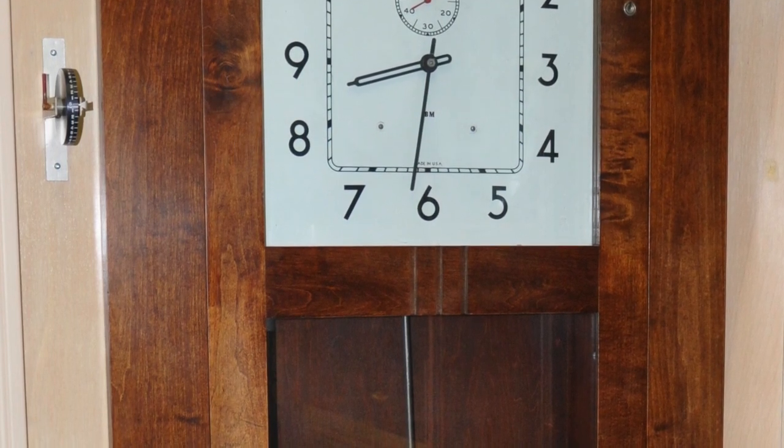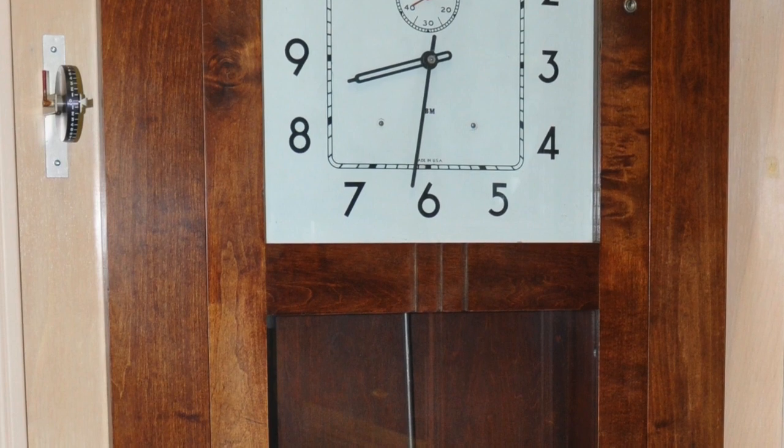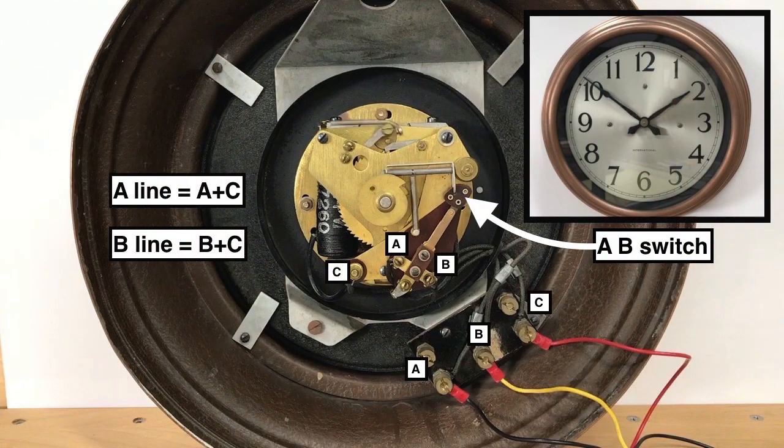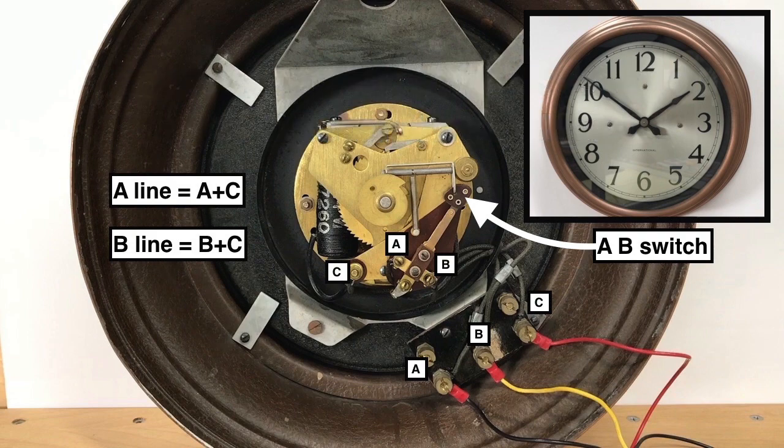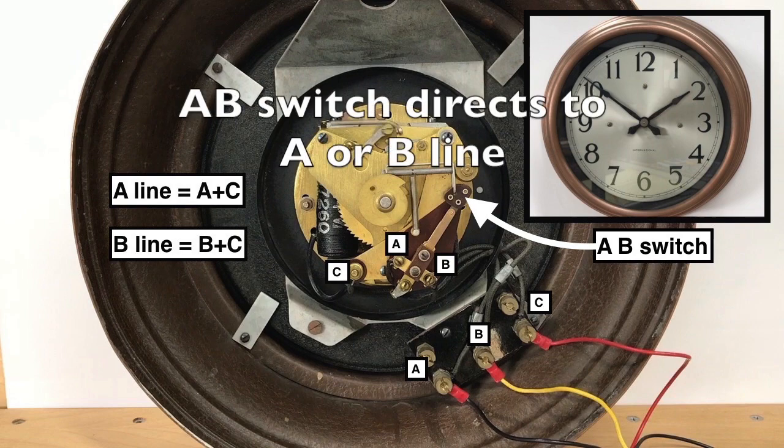The slave clock is not an independent timepiece. Slave hands are simply advanced one minute each time they receive an impulse from the master. This shows the slave wiring. The slave only accepts impulses on one line or the other. The A-B switch directs impulses to the A line or the B line.